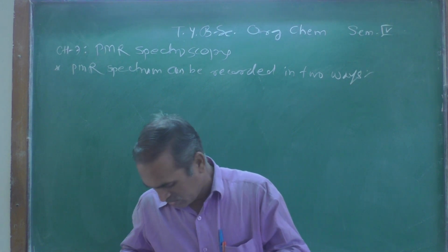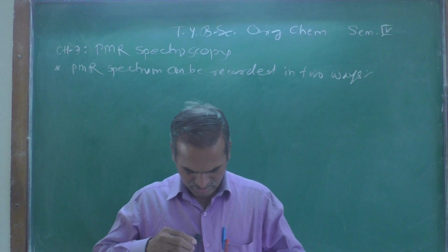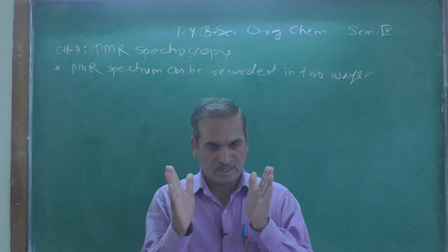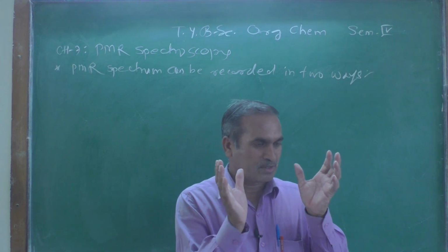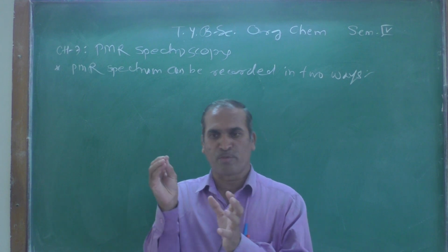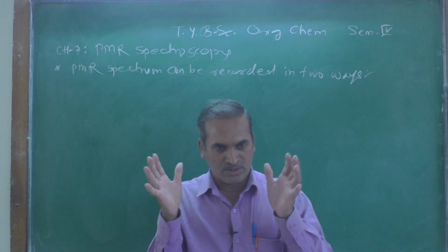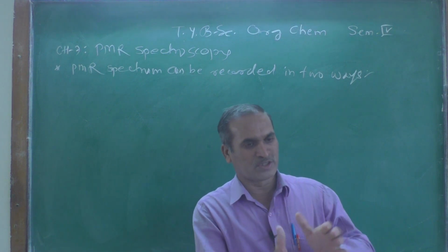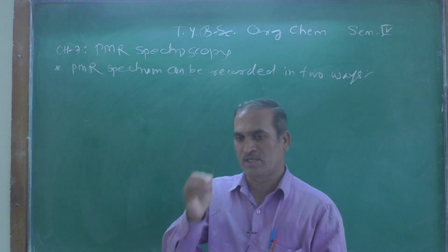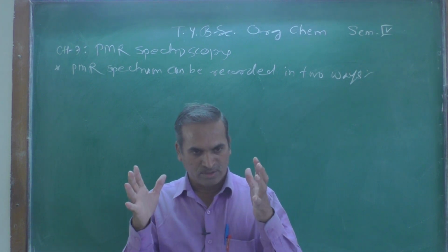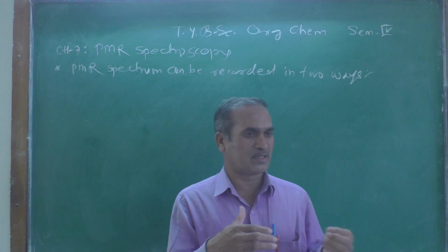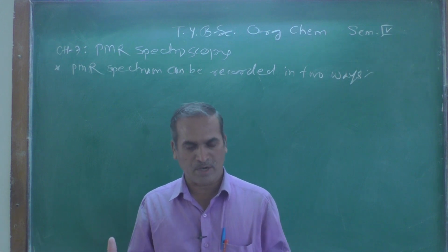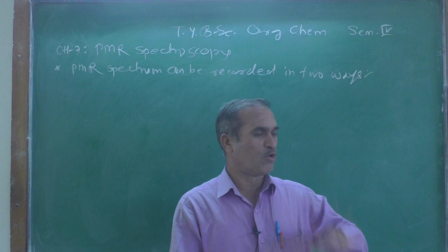In that, what we are generally discussing about these parts, right? Now, a strong, powerful electromagnet is placed, and homogeneity is required. Generally the electromagnet has a power of near about 14,000 Gauss, very powerful to get the homogeneity.